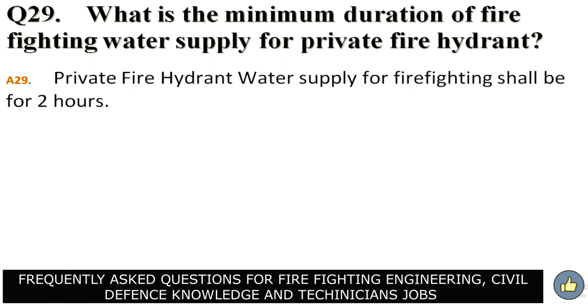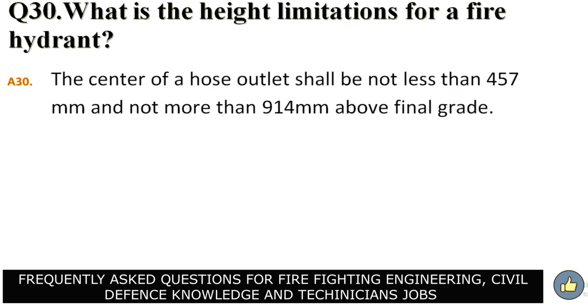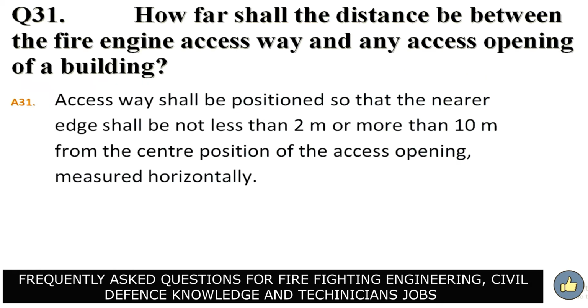What is the minimum duration of firefighting water supply for private fire hydrant? Answer. Private fire hydrant water supply for firefighting shall be for 2 hours. What is the height limitations for a fire hydrant? Answer. The center of hose outlet shall not be less than 457 millimeters and not more than 914 millimeters above final grade.